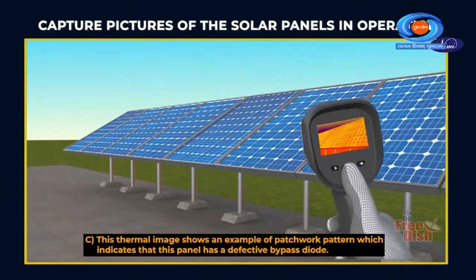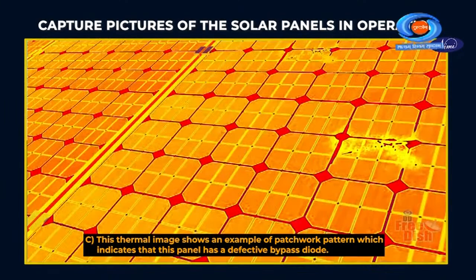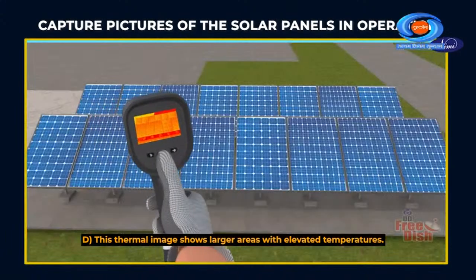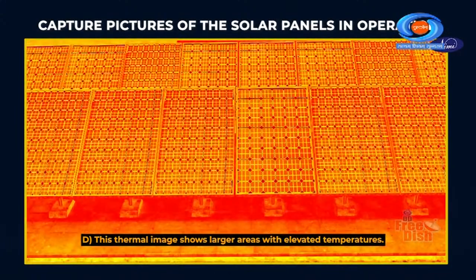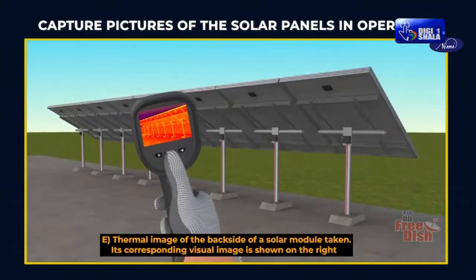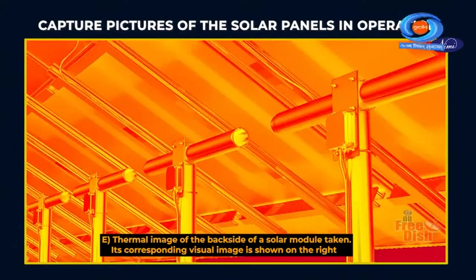This thermal image shows an example of patchwork pattern which indicates that this panel has a defective bypass diode. This thermal image shows larger areas with elevated temperatures. Thermal image of backside of solar module taken. Its corresponding visual image is shown on the right.